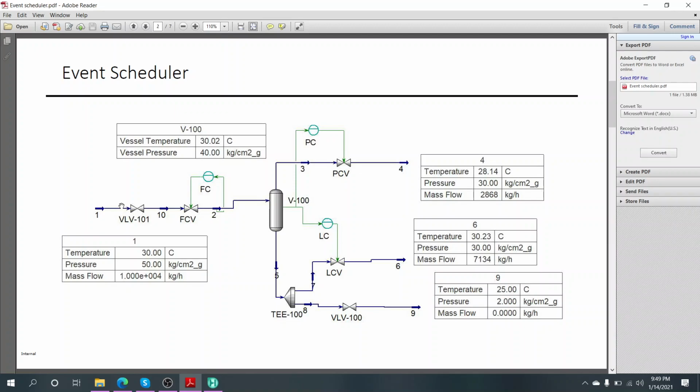So in some cases we did some simulation in such a way that instead of making it fast, we make it slightly slower, so that the created pressure wave does not exceed the design pressure of the line. Am I clear? Yeah, so the point of the valve is purely for isolation, not for controlling.